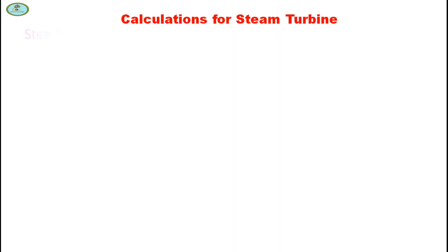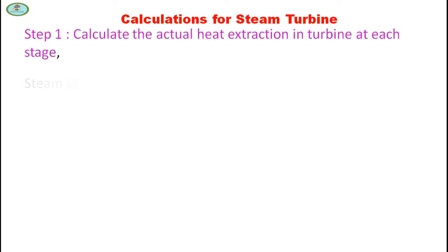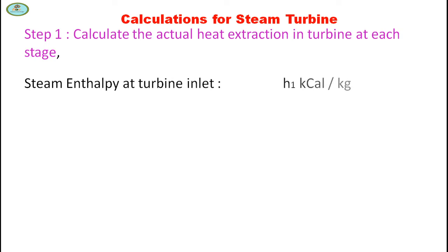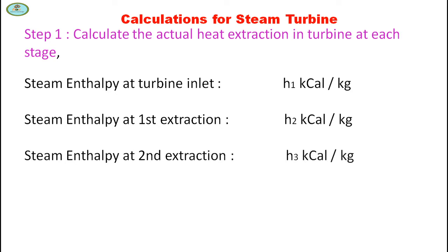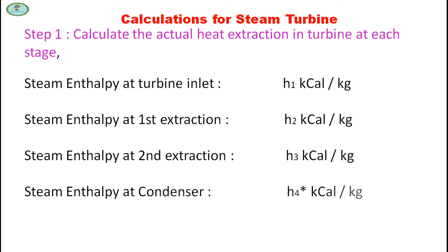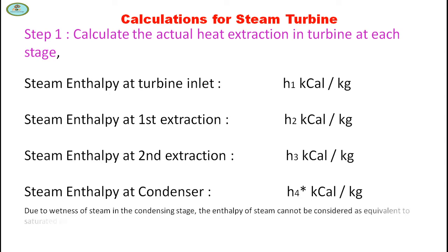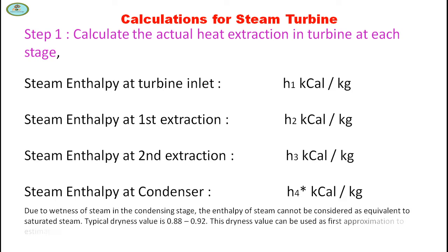Step 1: Calculate the actual heat extraction in the turbine at each stage. Steam enthalpy at turbine inlet is H1 kcal/kg, at first extraction is H2 kcal/kg, at second extraction is H3 kcal/kg, and at the condenser is H4 kcal/kg. Due to wetness of steam in the condensing stage, the enthalpy cannot be considered equivalent to saturated steam. Typical dryness value is 0.88 to 0.92.